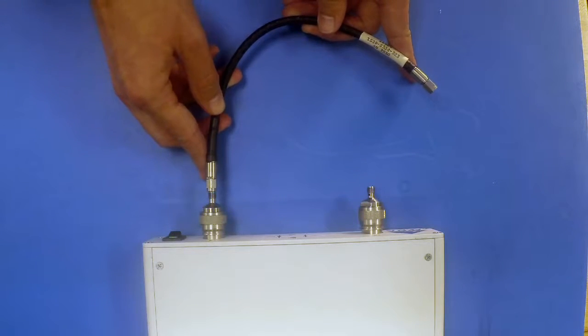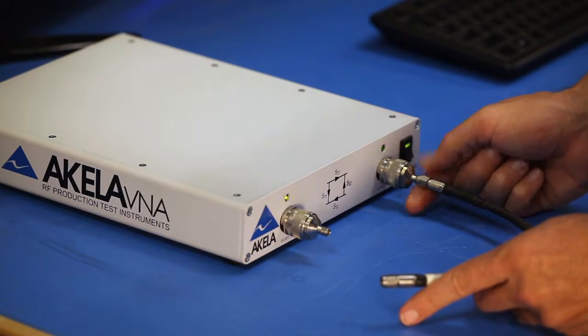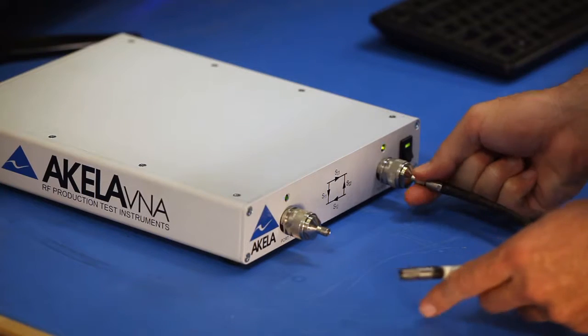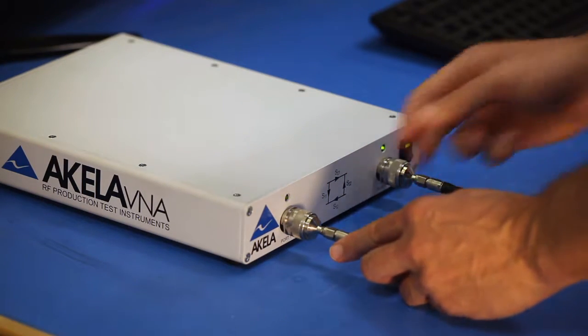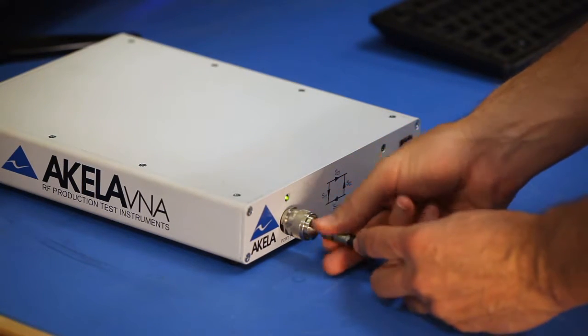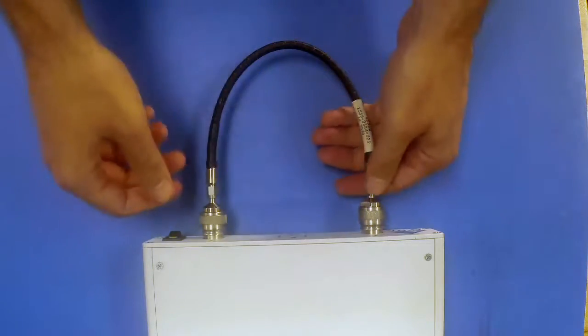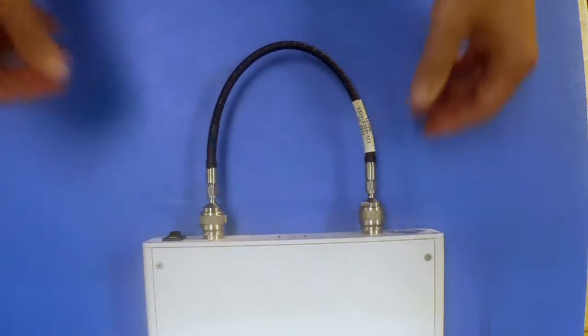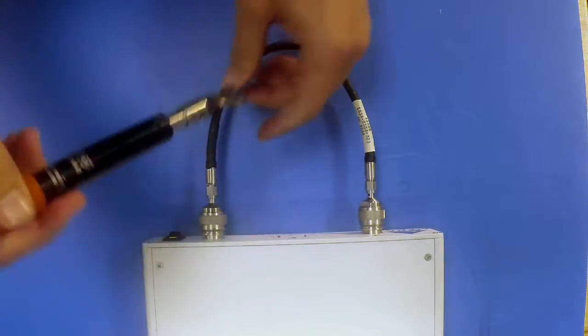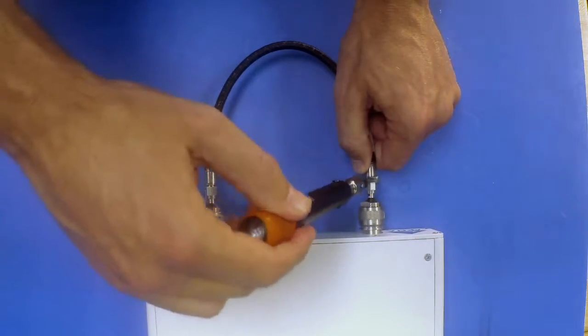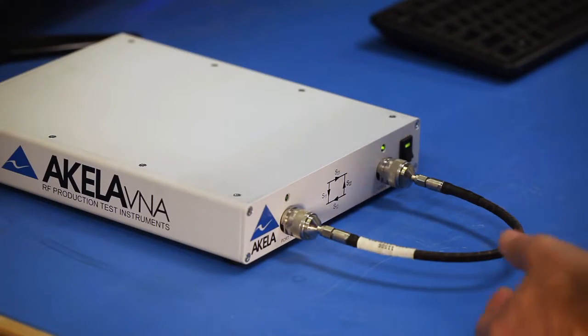In another video, we'll show you how to compensate for the fact that we've got a non-zero electrical length for our through. That's because the most common way of doing throughs assumes that your through is actually zero length. But for now, let's just get this on there and continue. Now, what I like to do is use a torque wrench to maintain a constant, repeatable connection between my calibration standards and the ports themselves.